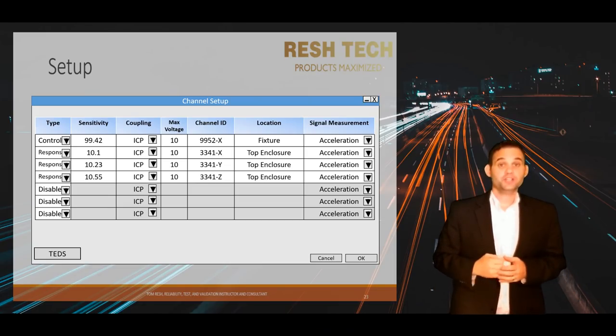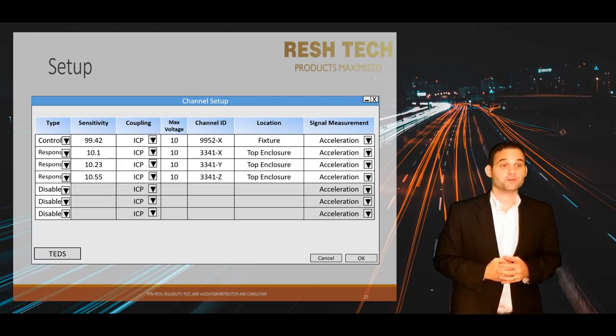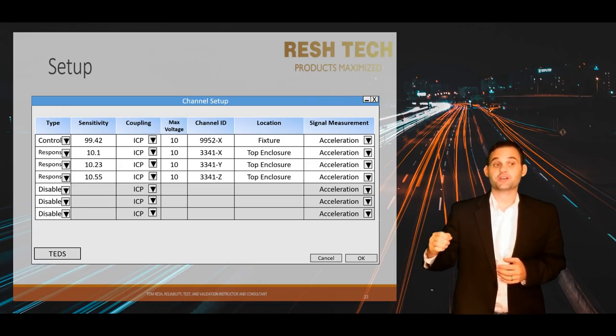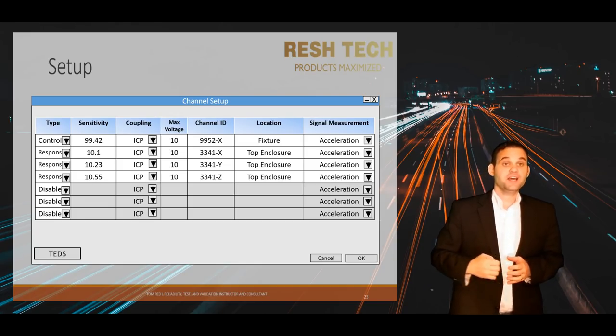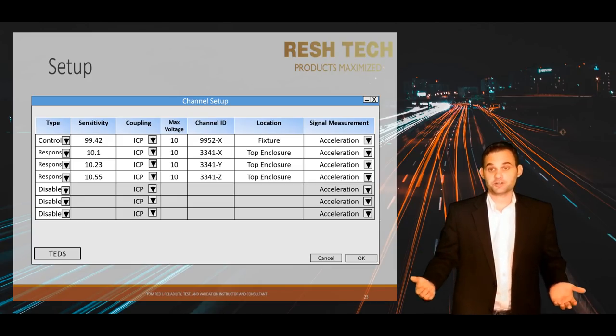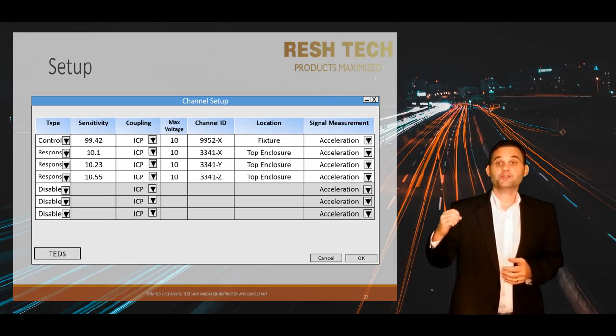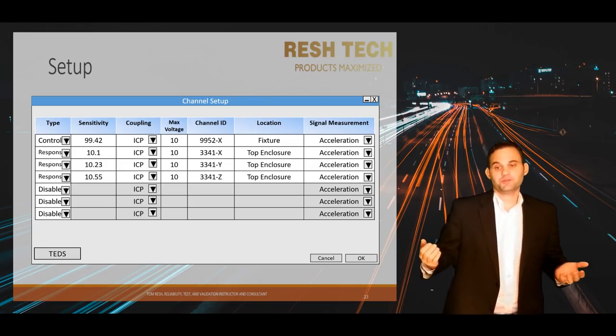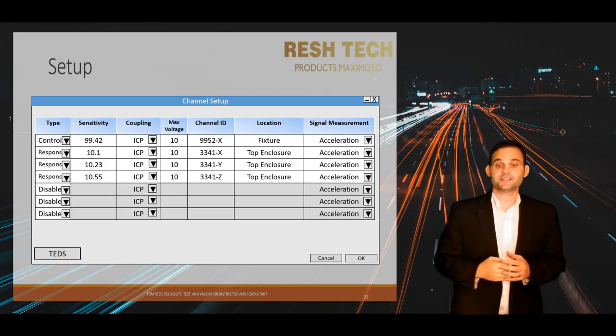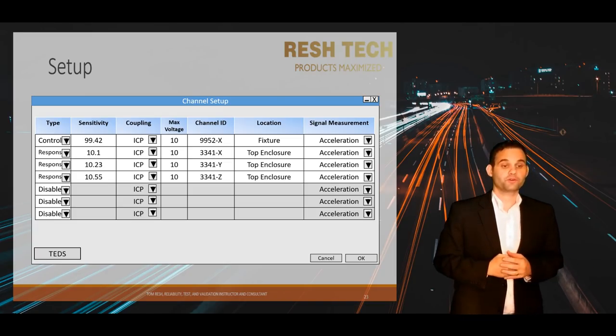The channel type column determines whether that channel will be used for control — which is the feedback your vibration controller uses to determine future output for the drive signal and maintain control to your test profile parameters. Another channel type is monitor or response — this is the accelerometer attached to your test unit, simply monitoring the response acceleration at that location. The last channel type is disabled, meaning you are not using this channel and want to disable it from being displayed or used as control.